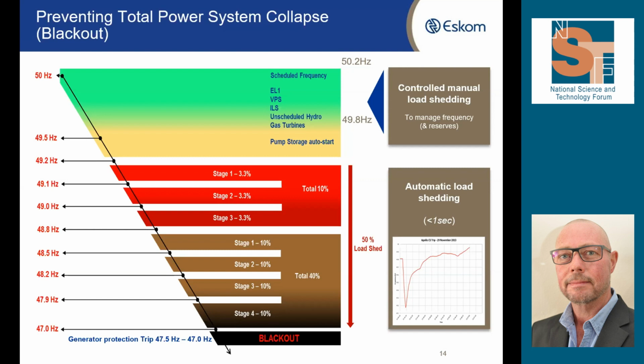With the frequency continuing to drop, we've then got 3 stages of automatic, what we call under frequency load shedding. And these are physical relays that are actually installed mostly in customer plant, where they would automatically sense a drop in frequency and then trip the plant that is connected to them. So similar to something that you'd find in your DB at home with an under frequency capability. We've got 3 stages connected there. The first one triggers at 49.2 hertz, the second one at 49.1 hertz, and then the third one at 49 hertz. And you'll remember from that graphic that I showed you around the capabilities of turbo generators, that 49 hertz becomes quite an important breakpoint for us as well. Connected to each one of these stages, we've got about 3.3%. So by the time we get to 49 hertz, we've disconnected about 10% of the load in the country. And that happens in less than a second.